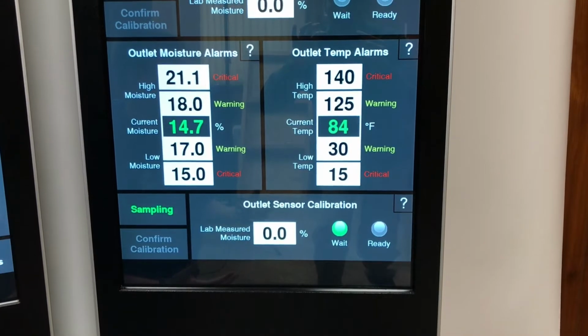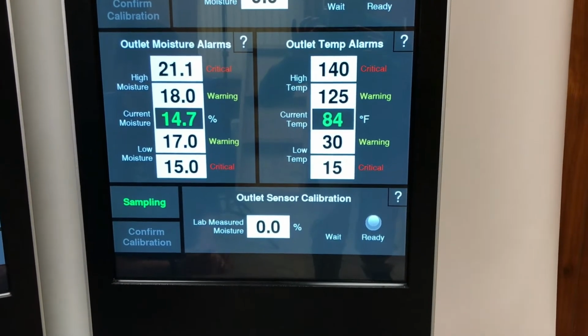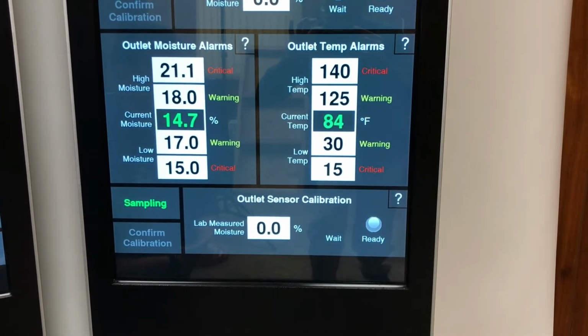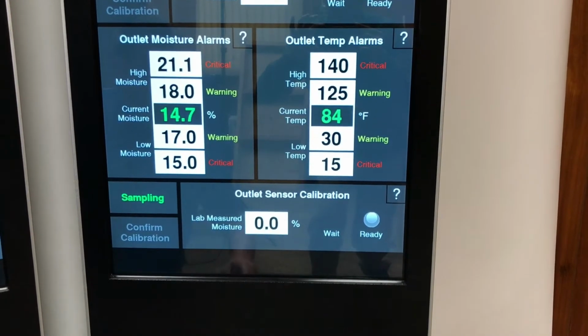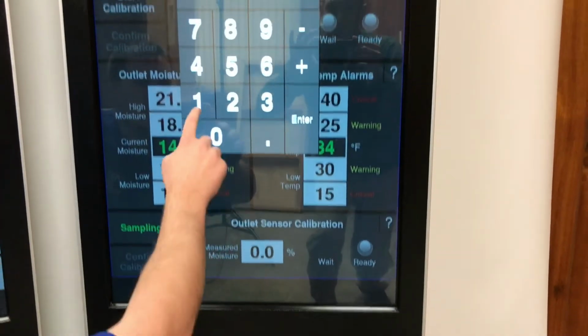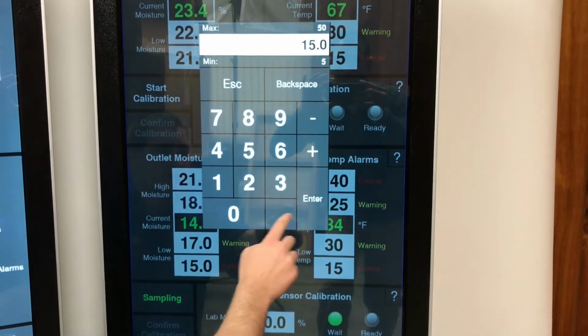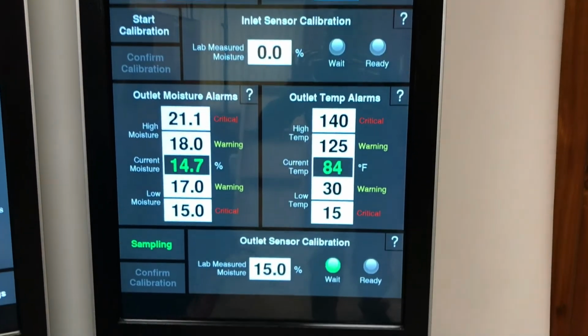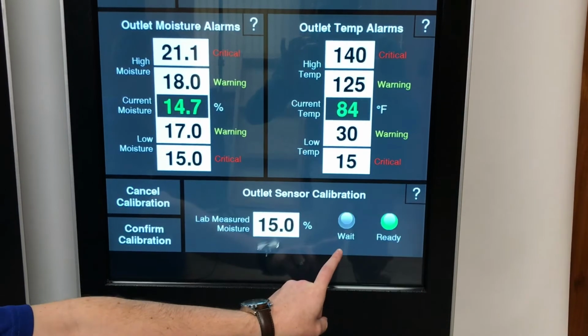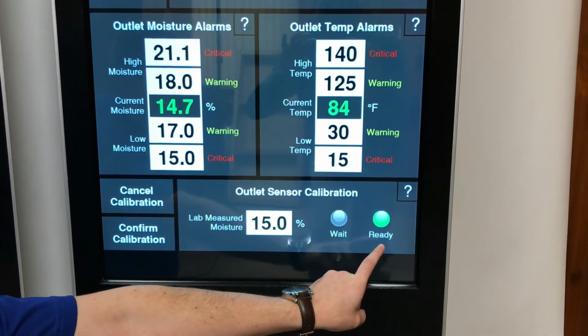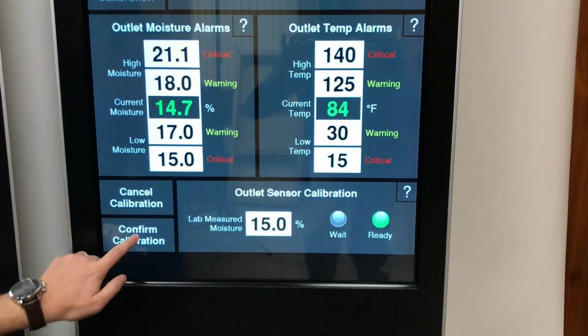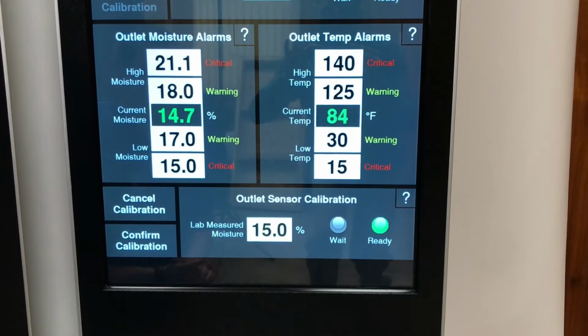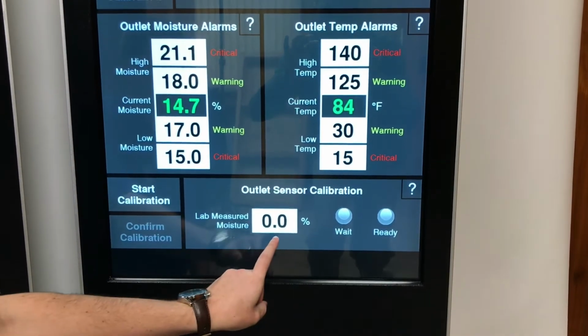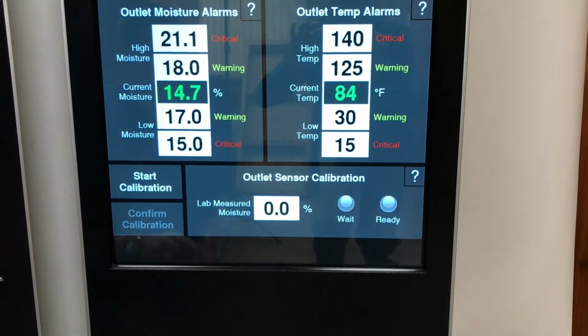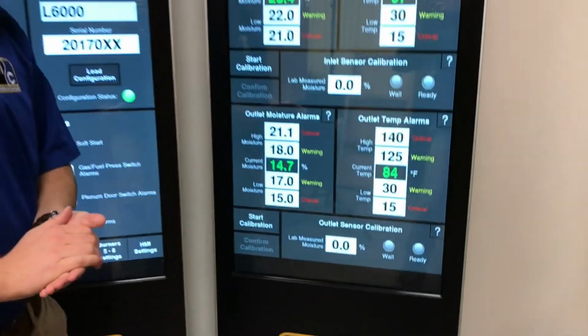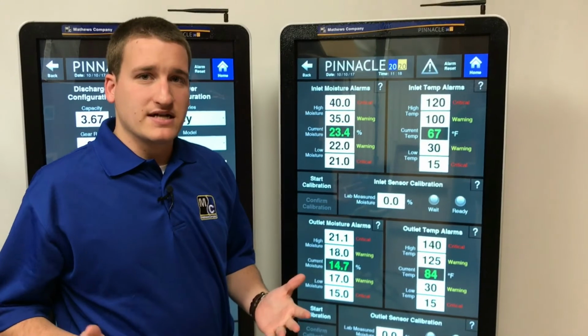During this time, you should go grab a sample of corn from the dryer, run it through your tabletop tester a few times and average the result, and enter the value you find here. Let's say you find 15.0. We'll have to continue waiting until the system's done, at which point it'll say it's ready, and you can now confirm your calibration. You'll know the value's been accepted when this gets written back to 0 and the confirm button turns gray. So that's the process on an AccuDry machine.